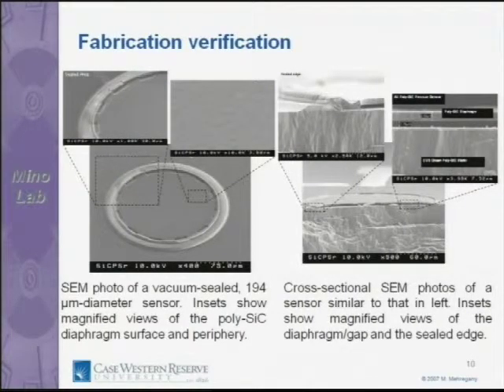In cross-section, you're seeing the silicon carbide wafer, the silicon carbide diaphragm, and the gap between the diaphragm and the bottom electrode forming the parallel plate capacitor. Here's a magnified view: the diaphragm is about 2 microns thick, this gap is about 1.5 microns thick, and then the substrate.